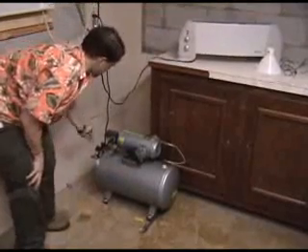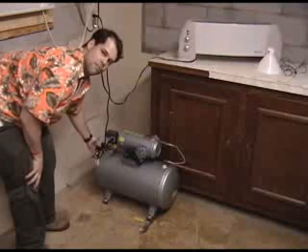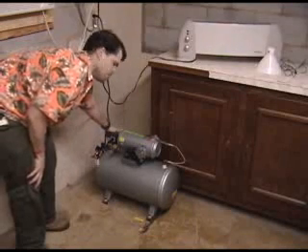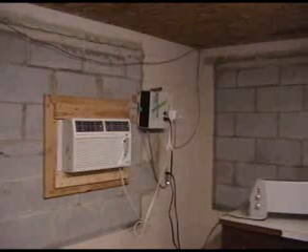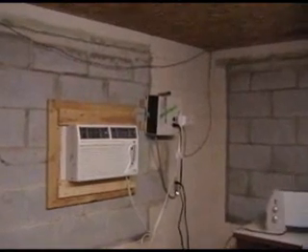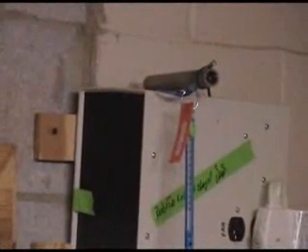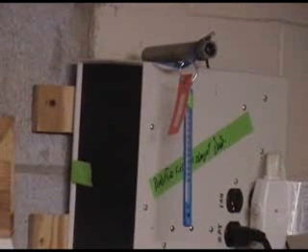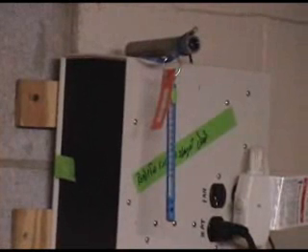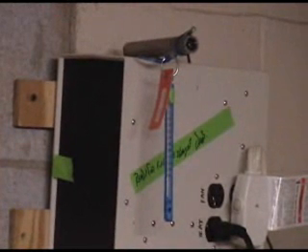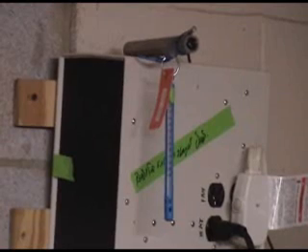Also, make sure that your gauges are reading 40 psi output, and that you might also have another gauge showing tank pressure. And today, because we're setting this site up, I'm wanting to check and make sure that the site temperature is also correct. And this is a picture of the actual temperature probe of the building. And I've also got my NIST thermometer standard there. And we're just going to check today, make sure it's still reading about right, that the average temperature it's putting out is true. And if we need to change that, we can.